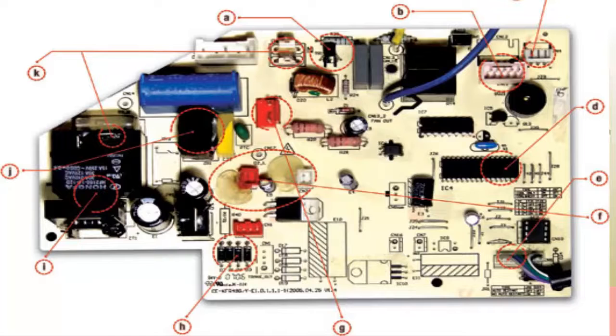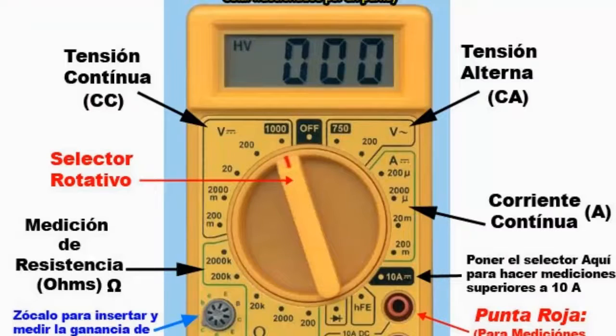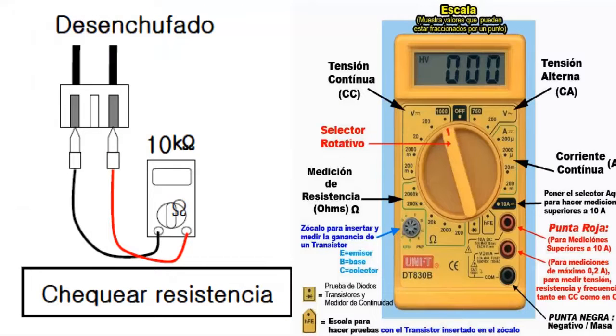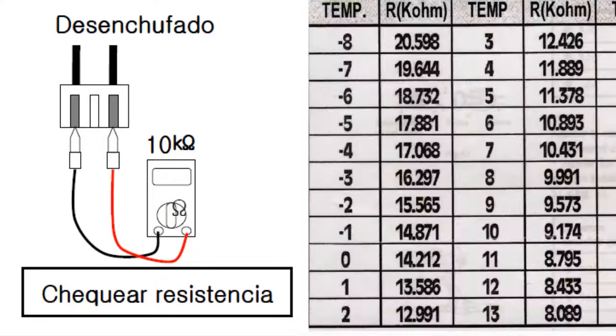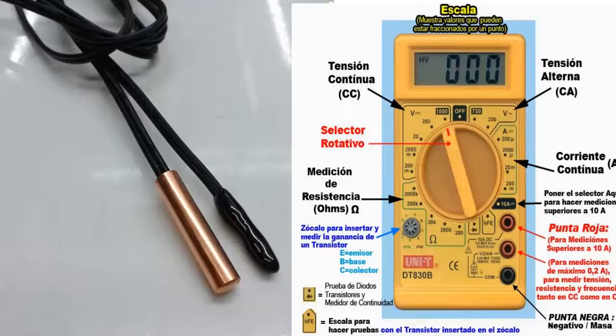Another recommendation is to always confirm the correct position of the sensor. It is also important to have a multimeter to measure the electrical resistance of the sensor. The reading is evaluated in kilo-ohms and it is verified if the resistance value corresponds to the value supplied by the manufacturer. In case the value is not met, we must touch or rub the sensor to add heat and verify if, when increasing the temperature, the resistance of the sensor drops.